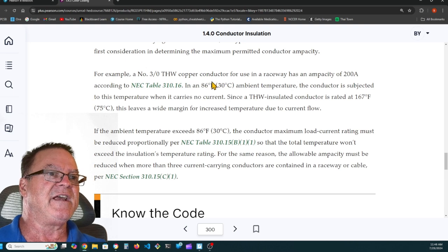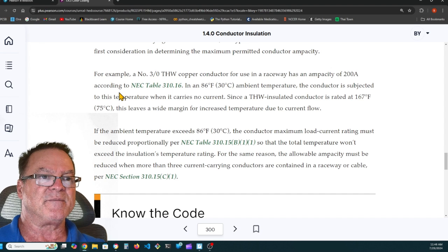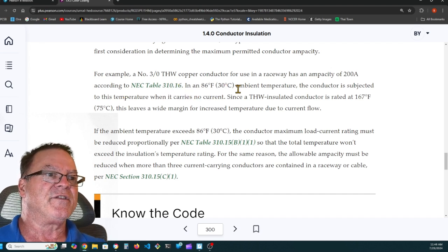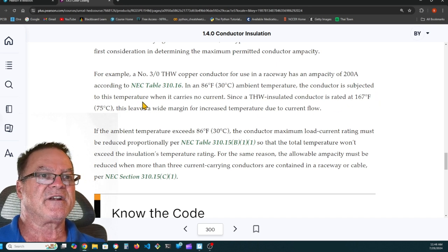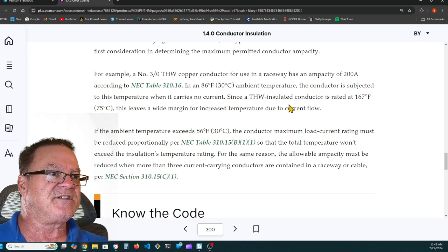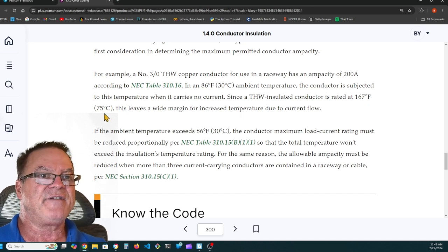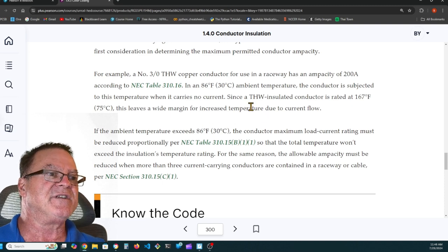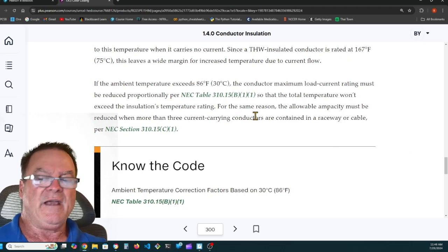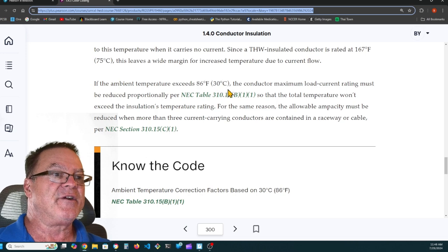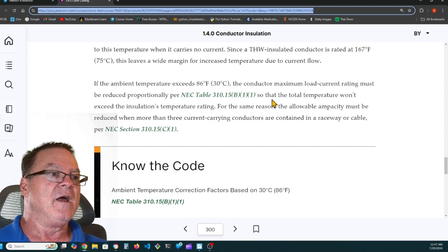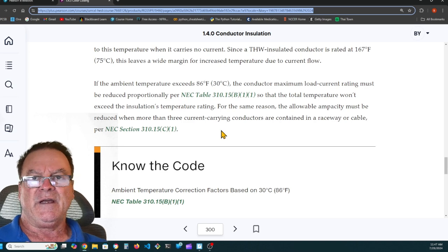For example, a number 3/0 THW copper conductor for use in a raceway has an ampacity of 200 amps, according to Table 310.16. In a 30 degrees Celsius ambient temperature, the conductor is subjected to this temperature when it's carrying no current. Since a THW insulated conductor is rated at 167 degrees Fahrenheit or 75 degrees Celsius, this leaves a wide margin for increased temperature due to current flow. If the ambient temperature exceeds 30 degrees Celsius, the conductor maximum load current carrying rating must be reduced proportionally so that the total temperature won't exceed the insulation's temperature rating. For the same reason, the allowable ampacity must be reduced when more than 3 current carrying conductors are contained in a raceway or cable. Again, it's about heat dissipation. We want the wires to be able to dissipate that heat.